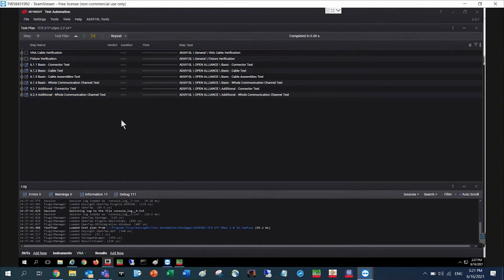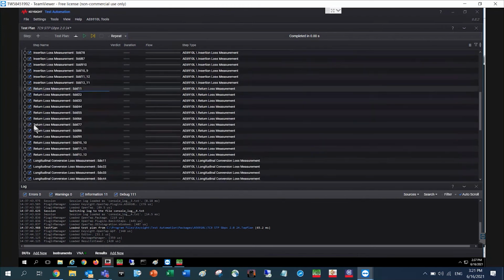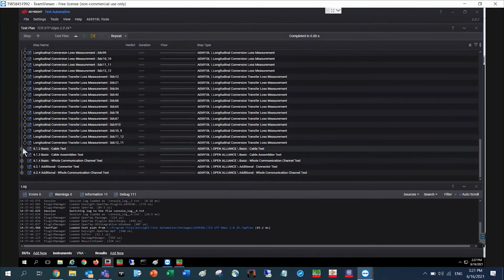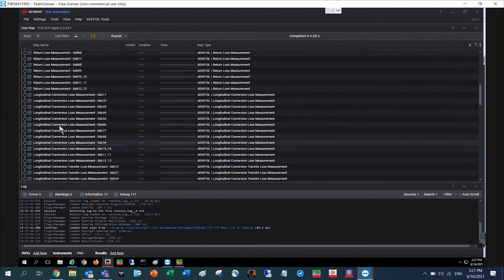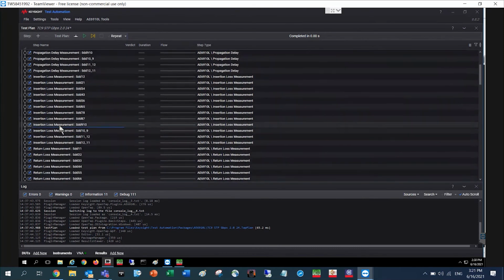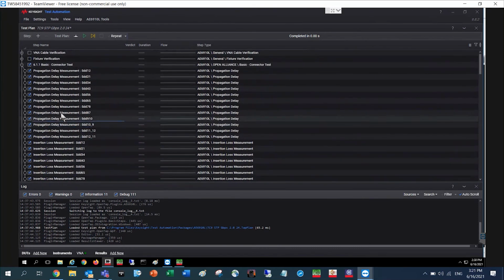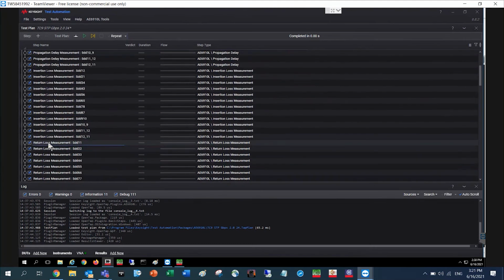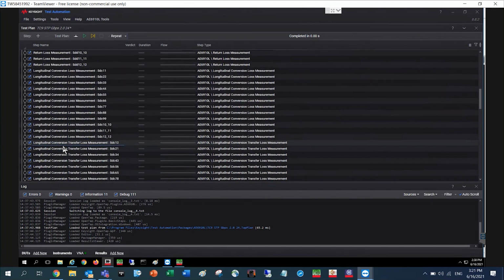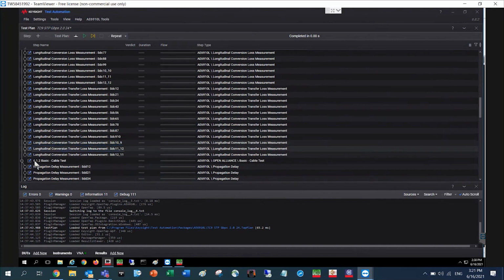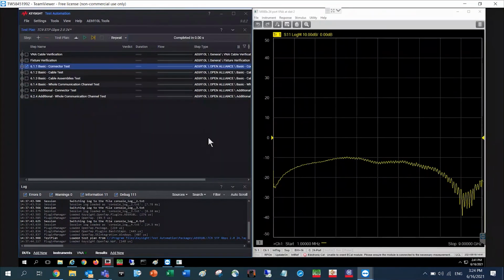If we open the windows, you can see that there are many different tests such as propagation delay and interference. As you can see, there's quite a lot of different things you can do, including insertion loss, return loss, mode conversion, and even bundle cable crosstalk. All this can be done all at once without having to remove cables or change the setup. After the calibration, we can now test.